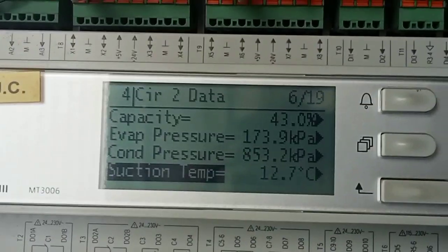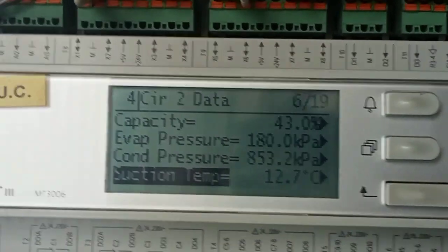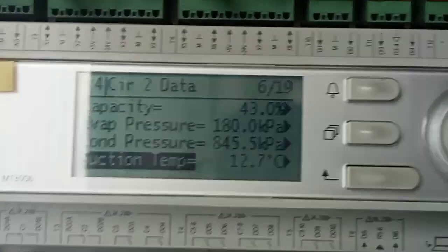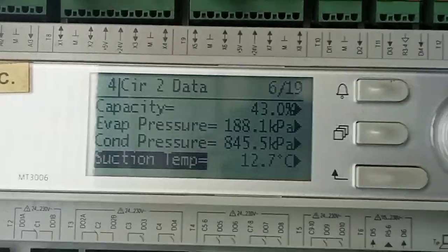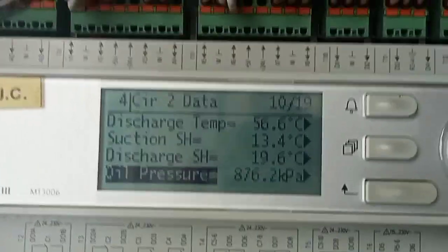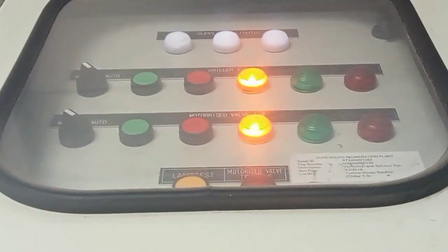Now the evaporator pressure is going very low. After about 5 minutes, it will automatically go to 200. Above 200 is okay. Suction, discharge temperature, everything can be checked. So far this is okay. See the chiller also.